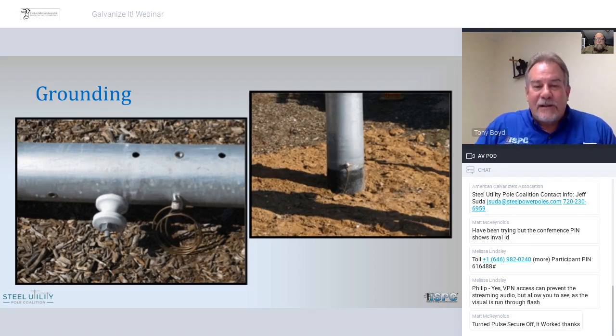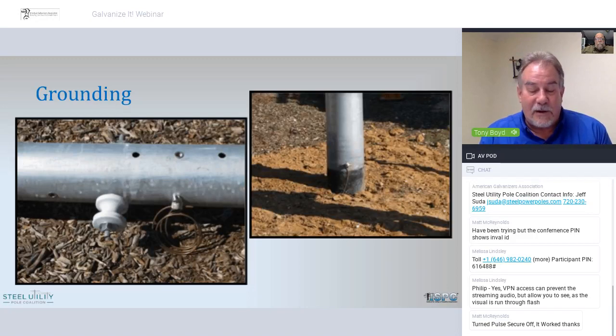Talking about grounding the poles, threaded inserts, grounding nuts can be placed anywhere along the pole where the grounding attachment needs to be made, for instance, at the system neutral. And then at the bottom, the bottom of the pole has a protective coating on it, so it does not typically make good contact with the soil. So an added ground rod would need to be used.